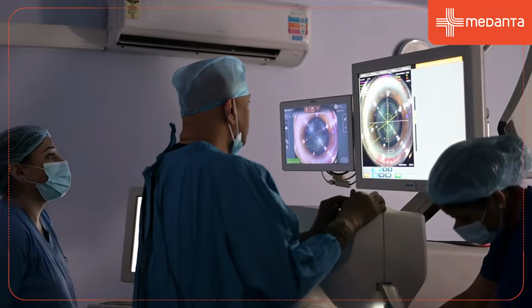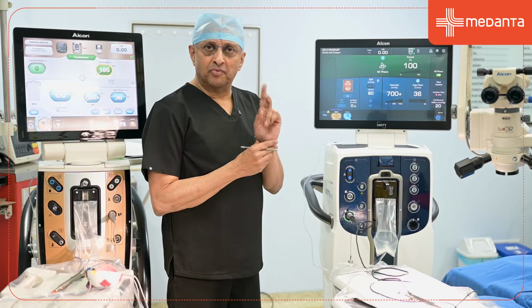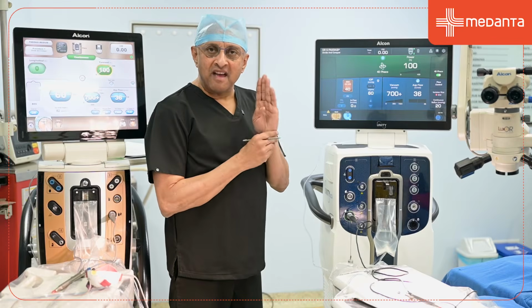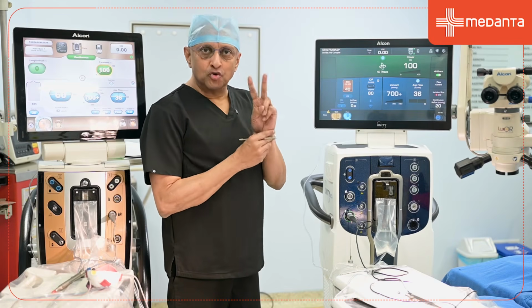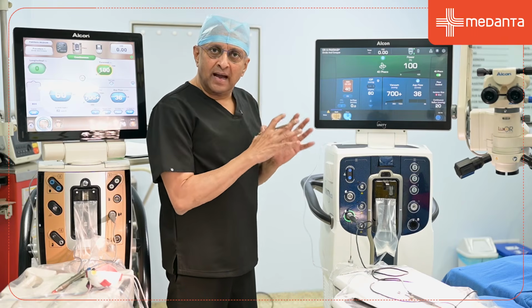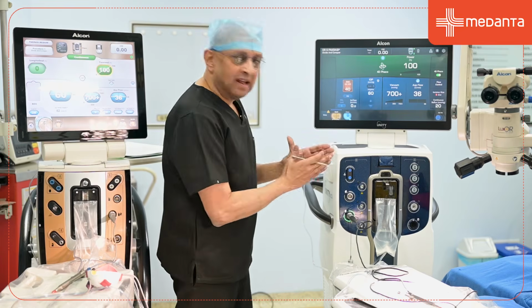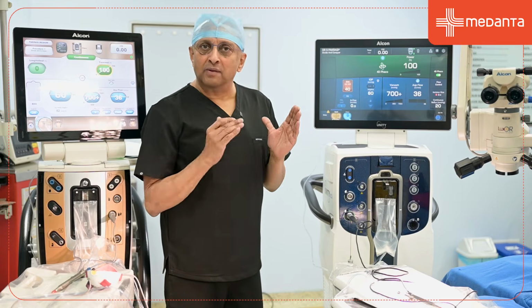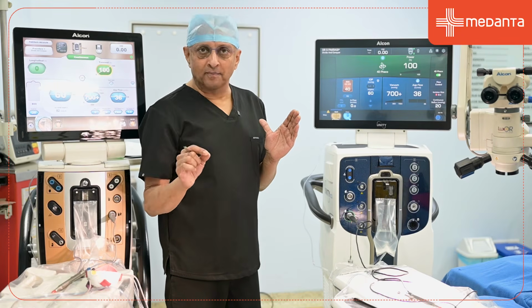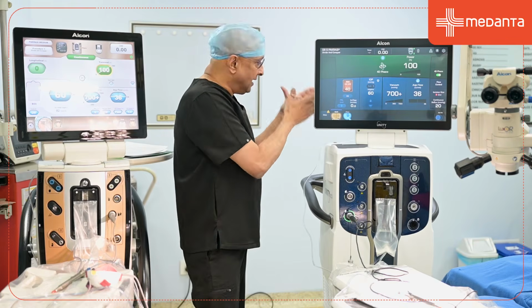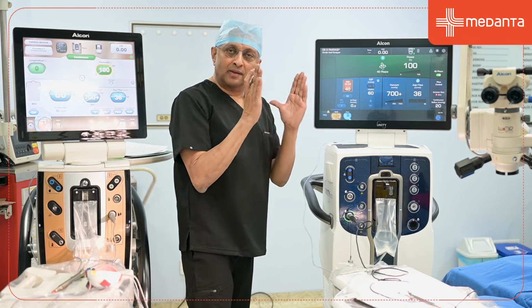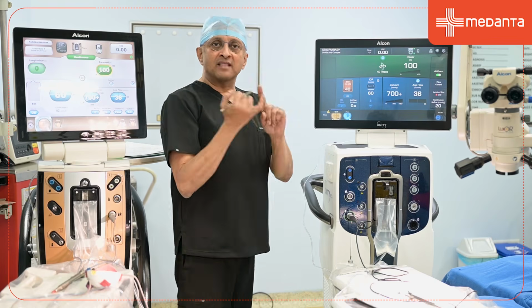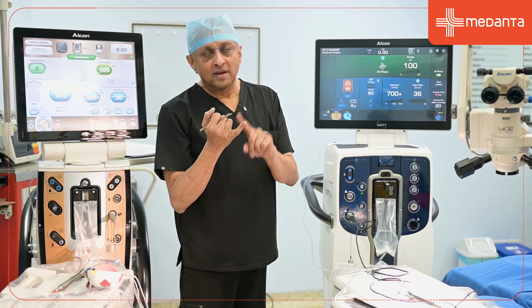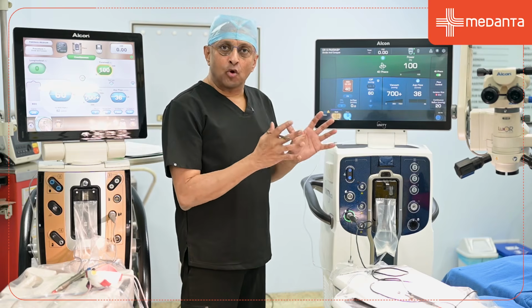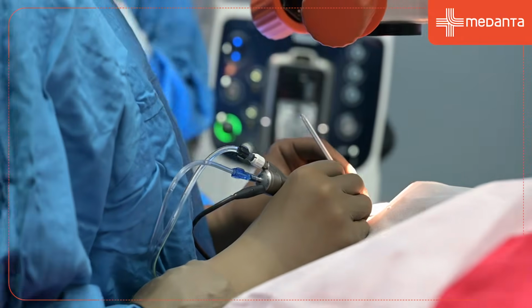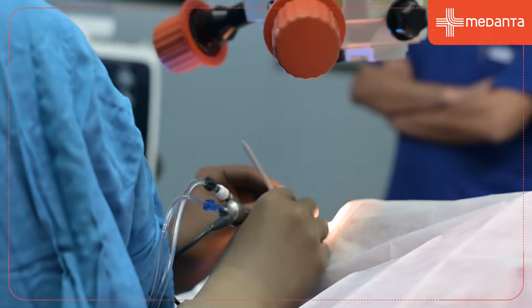1. Highly predictable surgeries which are precise, reproducible and very, very accurate. 2. There are real-time sensing mechanisms at every level of the machine, which makes the surgery much safer for cataract removal. 3rd, the fluid is in the box there at the back, and there are plates which sense. There are 2 pumps in this machine, the Peristaltic and the Venturi systems. 4th, they are controlled by real-time sensing mechanism which is available even at the tip of this probe.